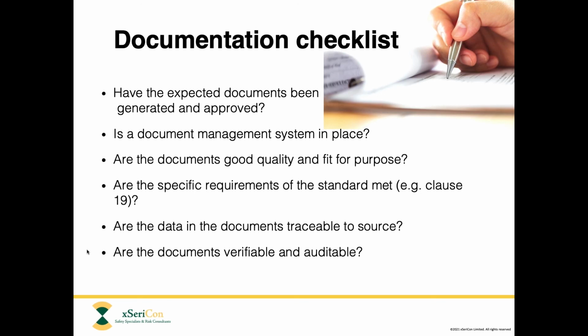Now, this can be one of the most difficult things to achieve in your documents, especially if you don't have traceability in mind right from the beginning when you first design the way the documents are organized and laid out. But the standard does have very specific requirements that all of the data in outputs from safety lifecycle activities needs to be traceable back to its source. So we would like to see that you're achieving that.